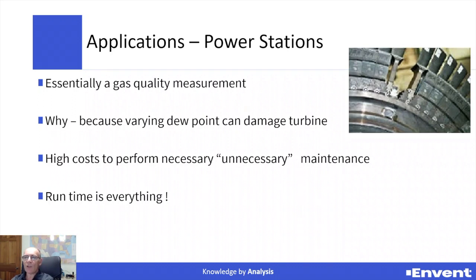So the measurement of hydrocarbon dew point determines the confidence of the superheat, which is typically 55 degrees, applied to the gas, and whether that is applying enough heat to ensure that a wholly gaseous mixture is being burnt and presented to the turbine. It's an important measurement.